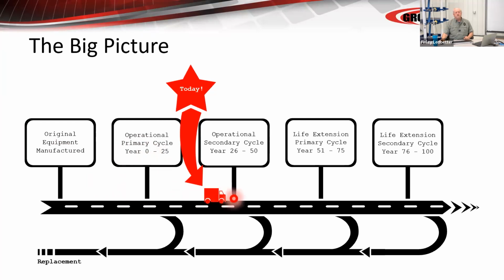Well, here we are now, almost 50 years into its life cycle from the 80s, and there's still no suitable replacement for the vacuum circuit breaker and for the low voltage power breaker. They keep talking about graphene and all kinds of advanced materials and SCRs and solid state breakers: buy a big SCR, turn it on, turn it off. But they started talking about that when I first went to my first seminar in Pittsburgh. When I first got into this business in 1979, I went to Pittsburgh for an OEM conference meeting, and they were talking about these solid state breakers they were developing and how soon they were going to come. And here we are, my whole lifetime later, and they're no closer to being able to interrupt the levels of power at the voltages they have to today, because those voltages and kA ratings continue to increase and escape them.